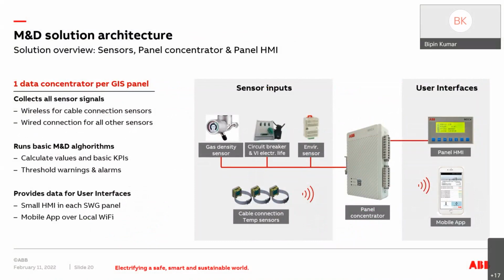That was from the sensor side, and we are also adding a few more components towards having monitoring and diagnostics capability. So we have a gas density sensor. We have circuit breaker and VI electrical life sensors in place. We have environmental sensors. We have temperature sensors. All these can be wired through an RS485 to our gateway, and through this we can have a visualization either on a local HMI, or we can take it to the cloud. We can view it through handheld devices as well.